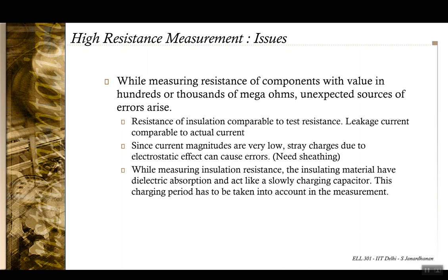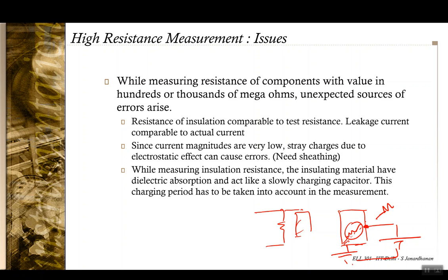Okay. In addition, when you are measuring insulation resistance of an insulator, let us say, okay, so you have an insulator, you don't expect current could go through the insulator. Let us say you're grounding this, you're having a terminal here and you're putting a voltage source across this and trying to measure the resistance in this path. Okay, but it actually would function like a capacitor and resistor in parallel.